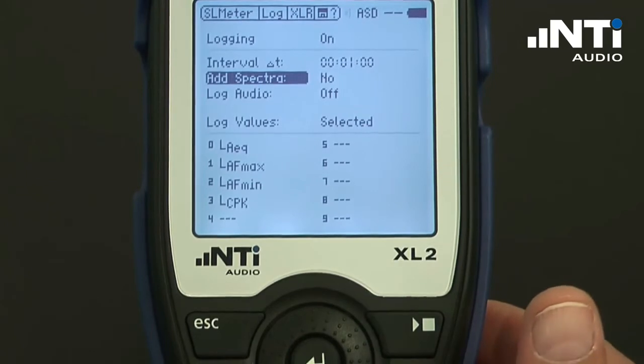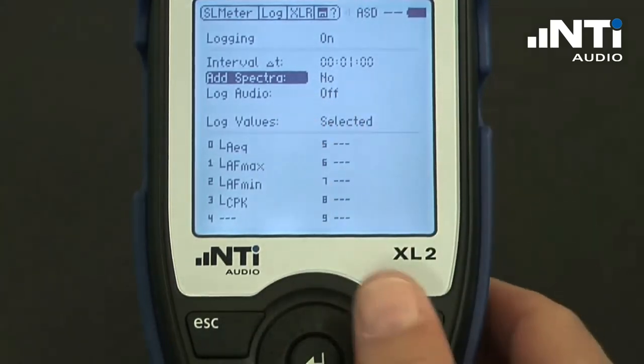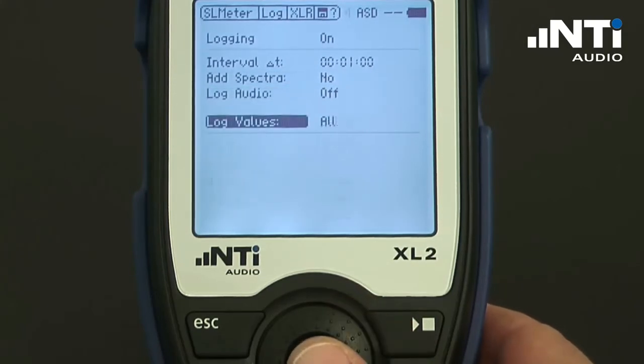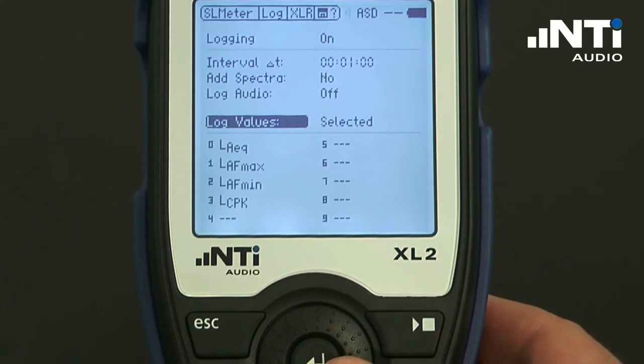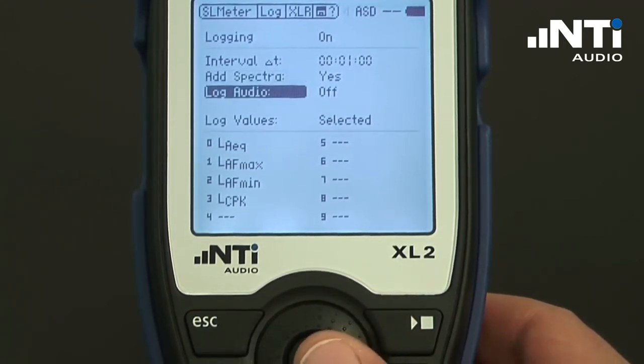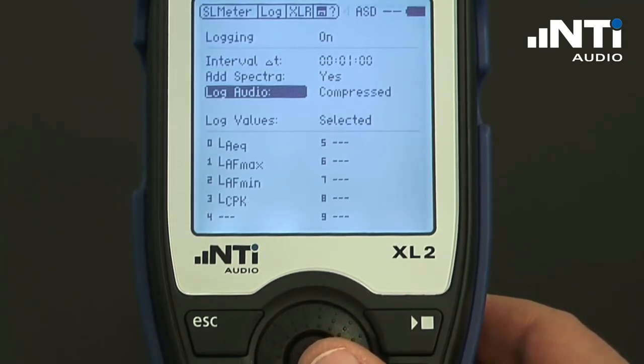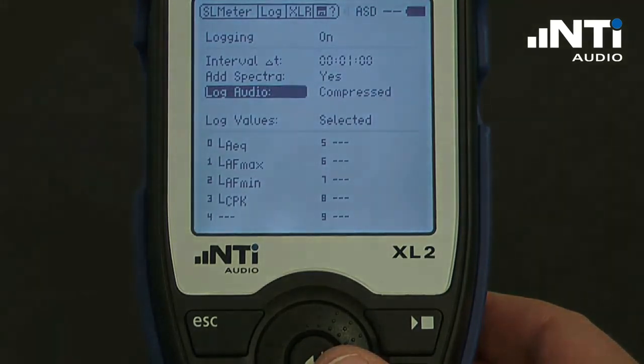In addition to the defined values displayed on screen, we can store all or a set of up to 10 levels after every log interval. We can also add spectral information, and in addition to that, we may also have the complete audio signal stored together with the measurement results.